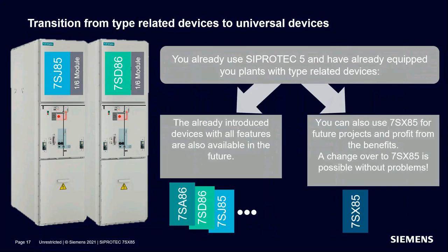The process for replacing defective devices by the universal device 7SX85 is easy, as I will show you in the next slide. All settings, connections, logics, and used protection functions, meaning the entire configuration of a device that needs to be replaced, can be exported into a so-called TEAX file. TEAX stands for Totally Integrated Energy Automation Exchange format. That is done via our engineering tool DIGSI 5, which is also used for the next steps I will show. By importing the TEAX file into the 7SX85 universal device, the conversion is almost finished. In a final step, the configuration must be downloaded into the physical 7SX85 device. A convenient, fast, and easy way to convert an existing configuration, right?